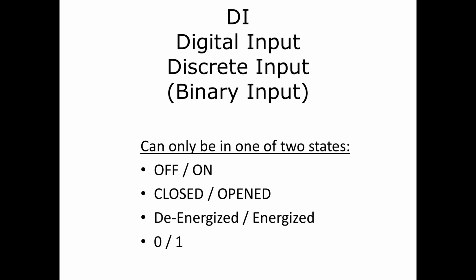It may be like a flow switch. It doesn't tell you exactly what the flow is, but if you get below 5 gallons a minute, that switch will turn on to let somebody know that you're getting low flow. It may not tell you exactly what the flow is, but it will tell you whether or not the flow is high enough. You'll also use those digital inputs to tell you if a valve is all the way open or if the valve is all the way closed. So, like I said, it can be in one of two states.